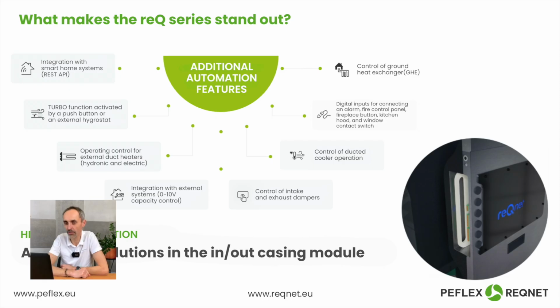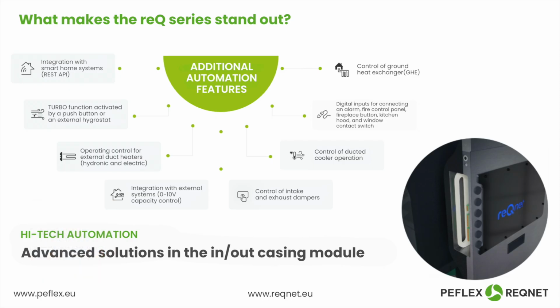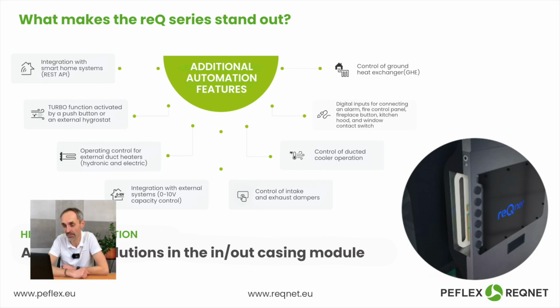As for this automation function, as I mentioned, here we have the possibility of integration with the REST API Smart Home System, or the option to connect an external doorbell button that triggers ventilation for us, or even an external duct heater, right? Whether it's a water or electric heater, whether as a secondary element, or integration with an external system via 0 to 10 volt performance control, or controlling the dampers on the air intake or exhaust. Controlling the operation of a duct cooler.